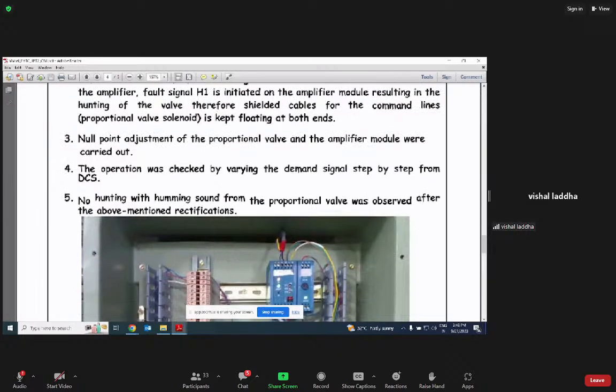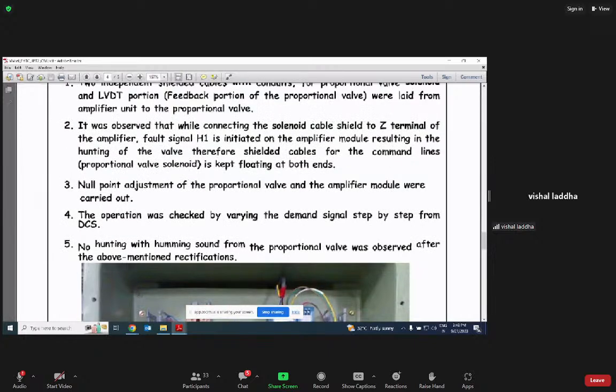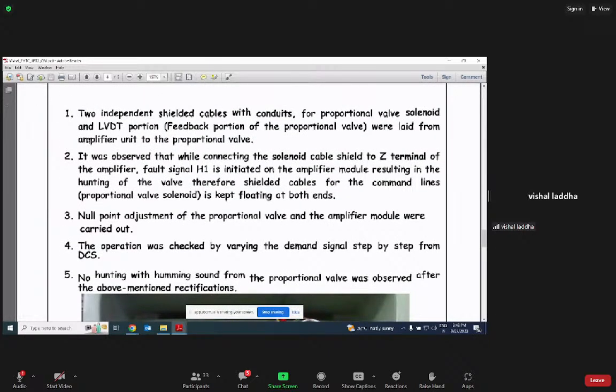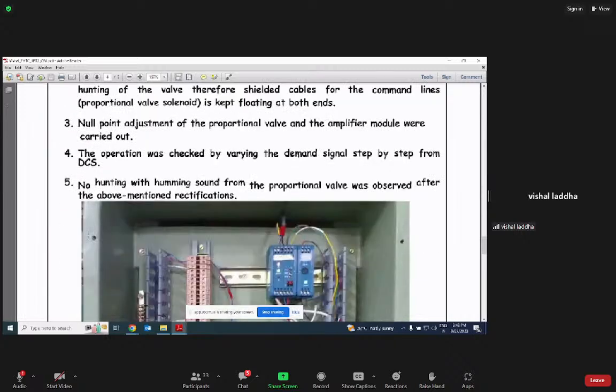Null point adjustment of the proportional valve and amplifier module was carried out. From this calibration port, the null point was adjusted. The operation was checked by varying the demand signal step by step from DCS. Now no hunting observed.